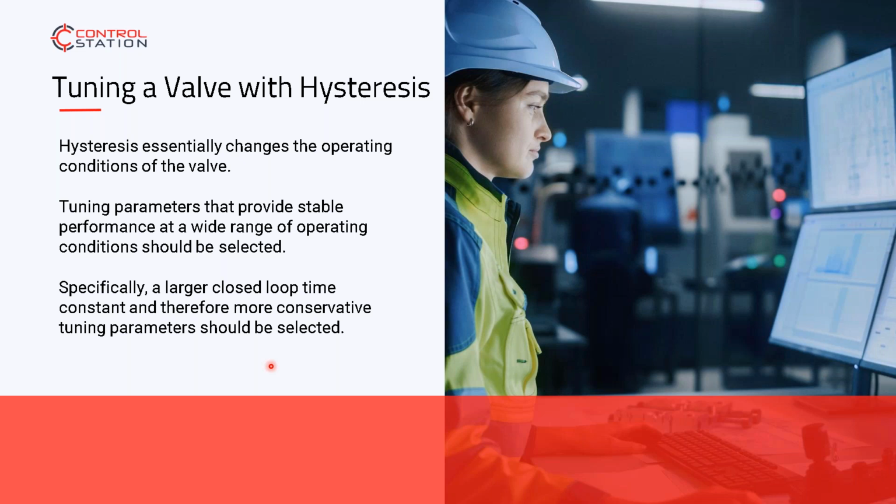So you're not doing root cause analysis, and you're not getting to that root cause and fixing the problem. Granted, the problem may be hard to fix, and it may take a shutdown to do it, but it's something that you need to build into your process to say, we can tune this, but we're putting a maintenance action in at next shutdown. We're going to address the mechanical limitations and weaknesses on that process.